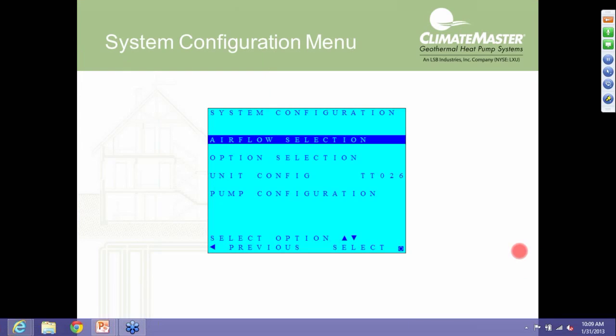Now, when you might have to go in and configure one of these boards, well, if you have to change out the control board for whatever reason, you'll have to go in and configure it for what model of heat pump you have and some other items that we're going to talk about: the blower type, pump setup, modulating valve setup, those kinds of things. We're first going to look here at airflow selection.